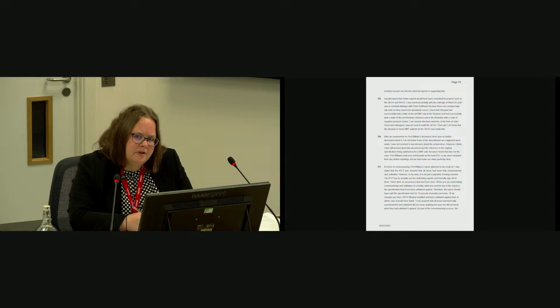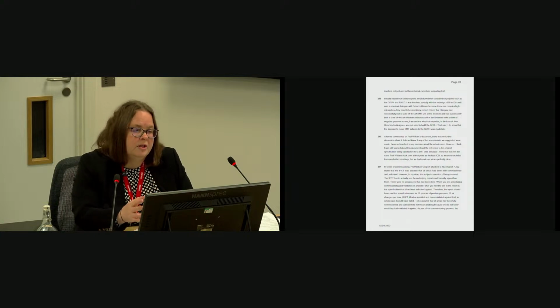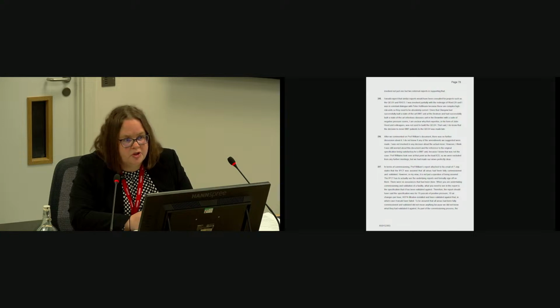And it's a bit different from water leaking directly from a chilled beam, because fungal spores are released in bursts. So you can have a water leak at one end of a ward, but patients at the other end are affected because of the burst of spores and how they travel. They're very buoyant, so they will move through the ceiling void. That's why we have measures in place for construction, because they will move very far. And if a ward isn't appropriately ventilated with HEPA filtration and protection, then yes, there can be ingress of spores.